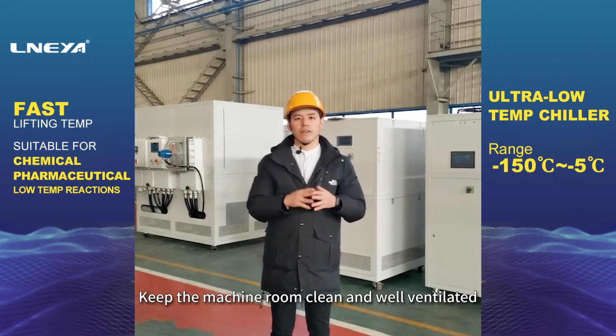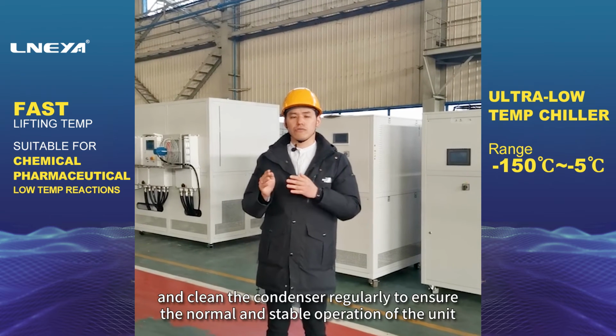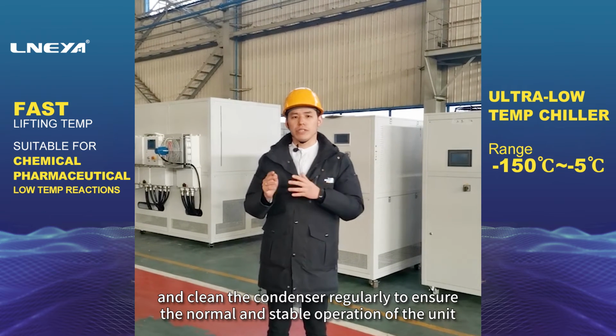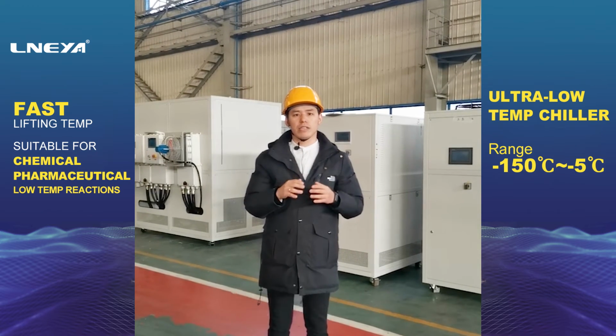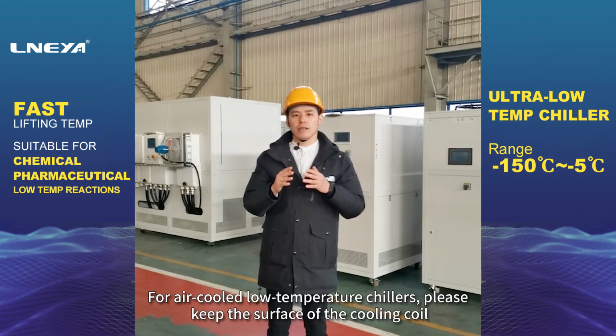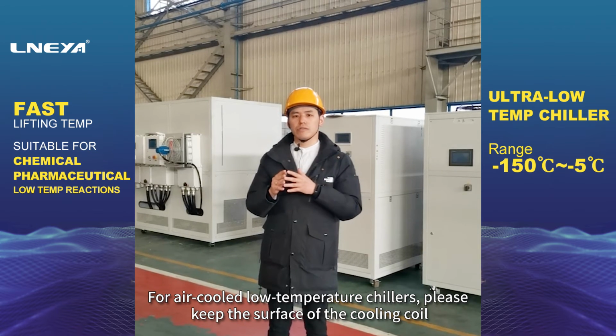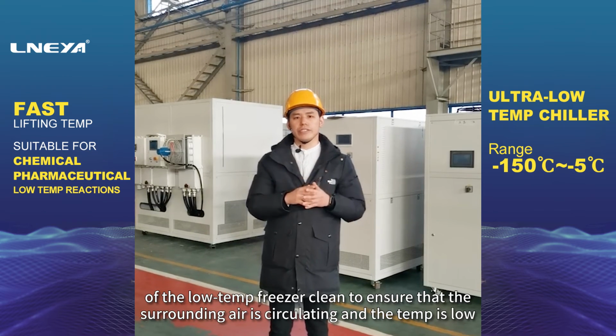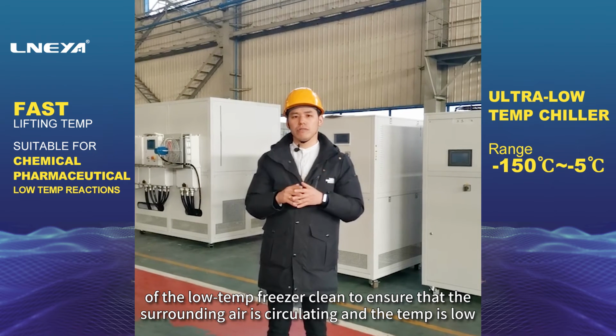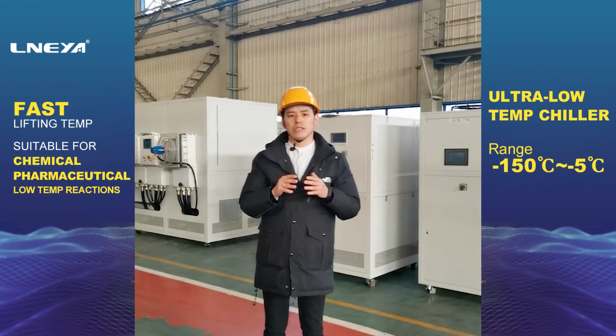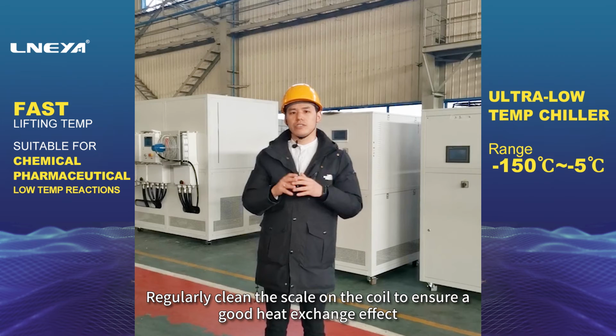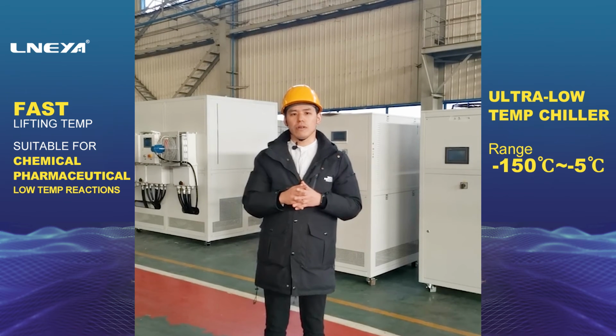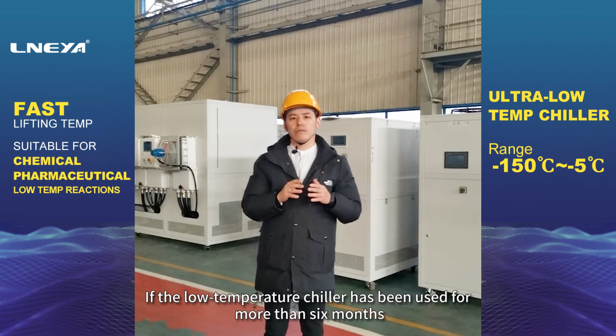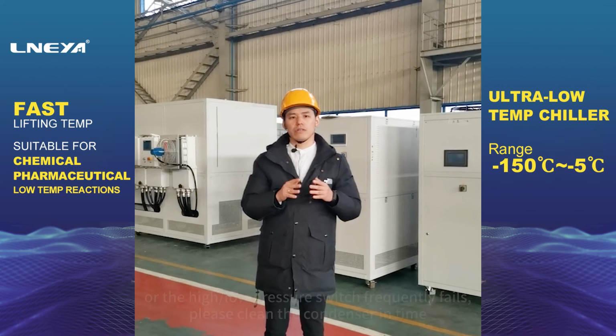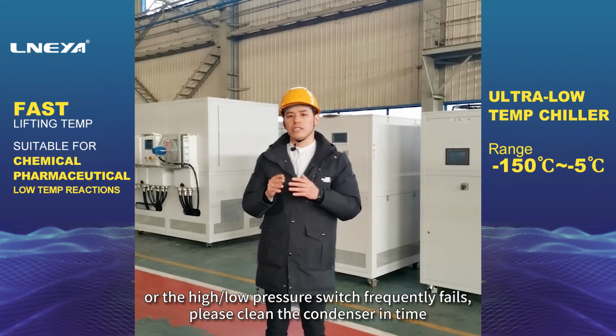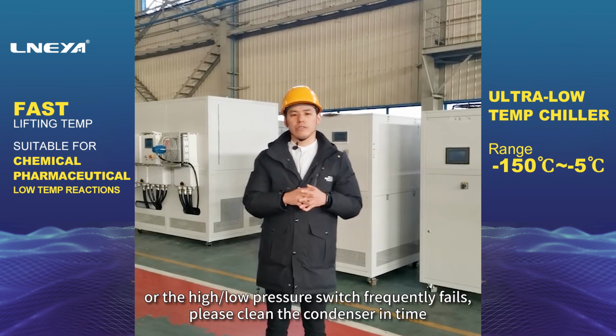Fifth, keep the machine room clean and well ventilated, and clean the condenser regularly to ensure the normal and stable operation of the unit. Sixth, for air-cooled low-temperature chillers, please keep the surface of the cooling coil of the low-temperature freezer clean to ensure that the surrounding air is circulating and the temperature is low. Regularly clean the scale on the coil to ensure a good heat exchange effect. Seventh, if the low-temperature chiller has been used for more than 6 months, or the high/low pressure switch frequently fails, please clean the condenser in time.